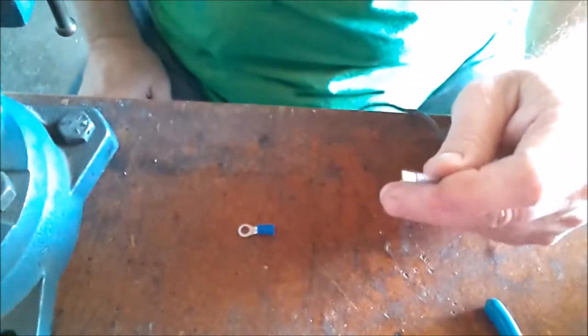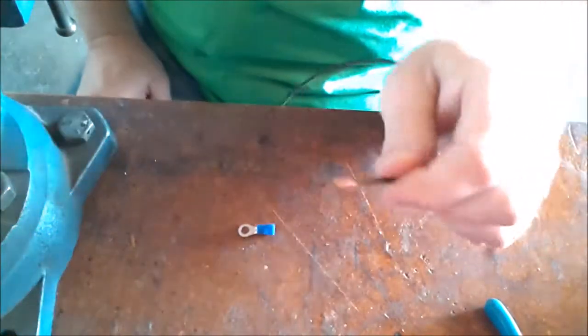Okay, now say, okay, so you got it in the end of your wire. Now with this type, you put it in and what you want to do is you want to have approximately a quarter inch, no more than a quarter inch, of wire sticking out. Then you just go into the right gauge wire hole that you're going to strip and you get about a quarter inch right there. And then all you do is squeeze, and the one side holds the insulation, holds the wire, the other side clamps down on the wire and strips it off. You get a perfect strip every time. So that's how you do it. Then you do a little bit of a twist on the end of the wire.